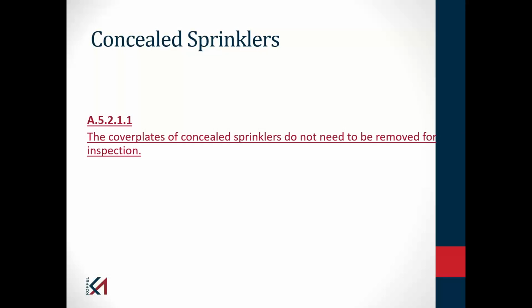The other thing we had considerable discussion on: some of you use concealed sprinklers. These are sprinklers that have a cap over them so that I don't actually see the sprinkler. I just see this circular cap up at the ceiling. A contractor came to us and said, I had no evidence of corrosion, but I happened to remove the cap from one of these concealed sprinklers, and I saw that the sprinkler was corroded. So we debated that issue, and we added an annex note to say, no, the cover plates, the caps, do not have to be removed for the concealed sprinklers.